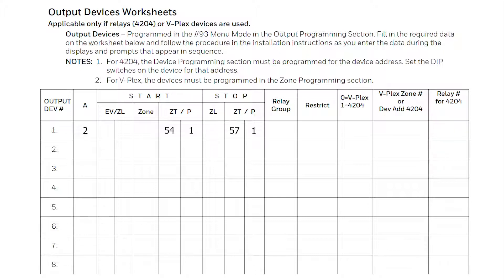Choose your relay type, either 0 for VPLEX such as the 4101SN, or 1 for ECP such as the 4204. Press star. If your relay is the 4101SN, enter the zone number that this module was programmed to. If your relay is the 4204, enter the device number you addressed it to, then press star. Also, if your relay is the 4204, after entering the address, you will be asked to enter the module relay number. This is the position of the relay, 1 through 4, on the 4204. Verify your programming on the summary screen, then press star.